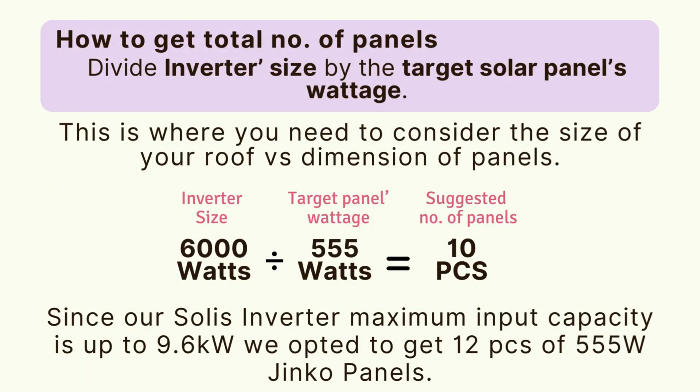Since the maximum usable PV input power of the 6-kilowatt hybrid inverter is 9.6 kilowatts, we increased to 12 panels. If we were to maximize the maximum PV input power, we could go up to 20 pieces, but they wouldn't all fit on our roof.